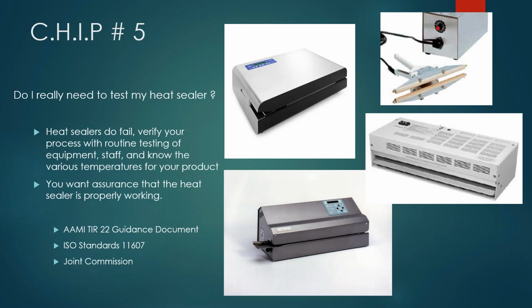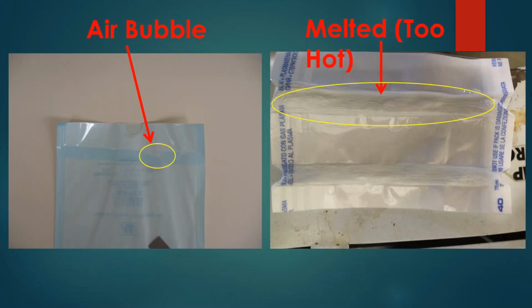And that's a big thing now. ST90, I believe, is a document that you're going to start hearing more and more about. And it starts to talk about IQ, OQ, PQ, and making sure that this machine functions as it was intended and provides the seal that it should, is part of that performance qualification. And you can already see that AAMI has a TIR, which is a guidance document that talks about it. ISO has a standard as well. And then it is something the Joint Commission can look at.